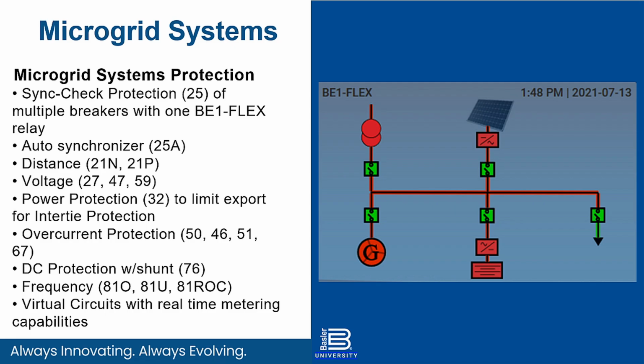Another thing that is important to remember about microgrid systems is when systems are non-radial, so when they do not have just a single direct path from generation source to load, the overcurrents can have difficulties seeing different fault conditions because those currents might cancel each other out. So things like distance protection, bus protection, and directionality become more and more important because standard overcurrent just can't see it electrically.